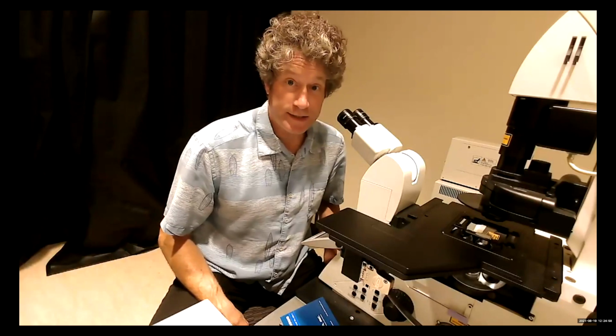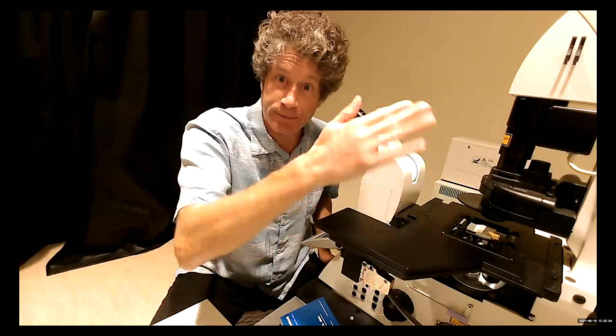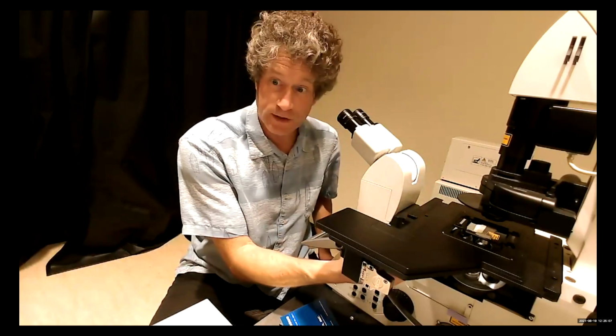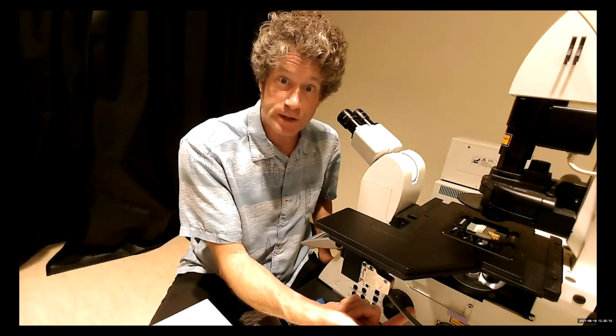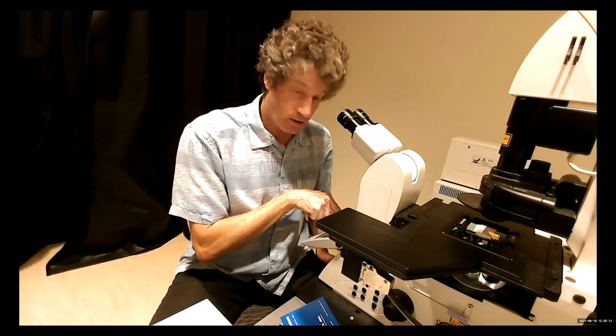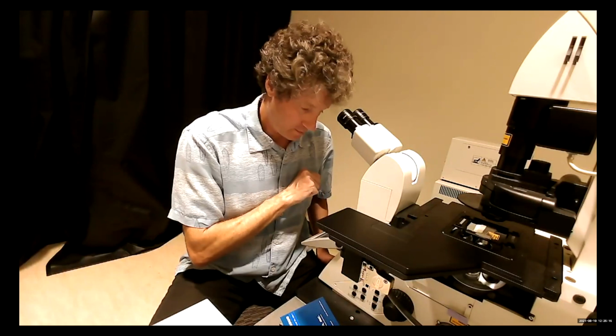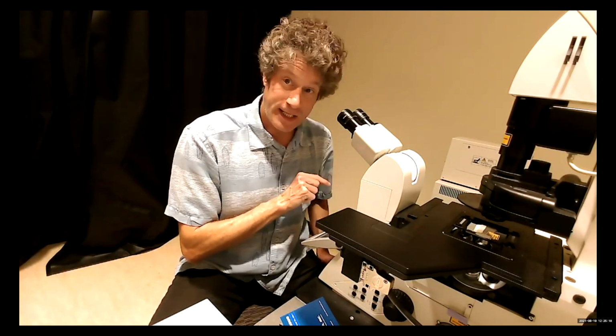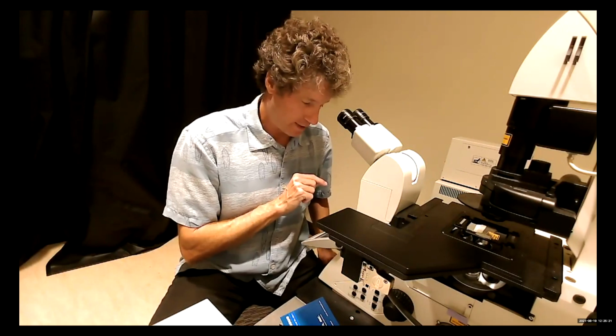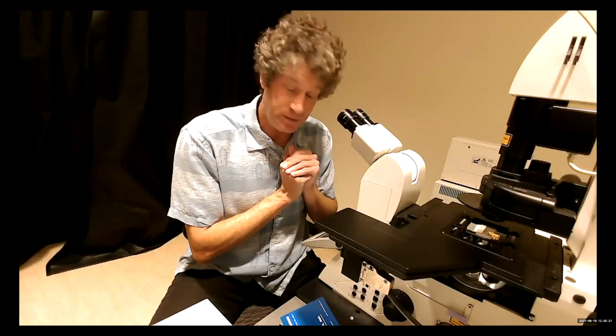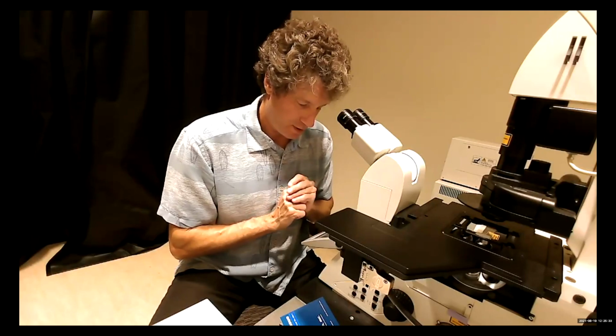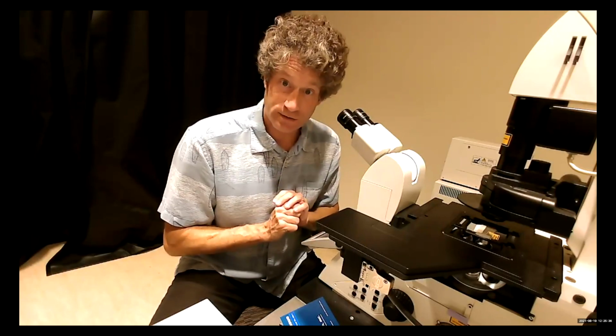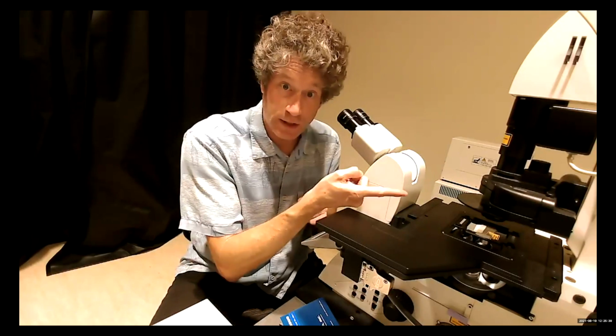Okay, now I'm gonna find the sample, which you should have seen on another video, but I'm gonna do it again. Basically, the sample is here, right? It's upside down. You wanna make sure the objective lenses, which are underneath here, should be 10X. That's here on the little lens icon. It says 10. Then you go up to the next icon, there should be BF that has a contrast, like a moon with a contrast light and dark on it. That should be BF, and TL shutter should be yellow. Then the very top, the TL axis should be clicked, and that allows all the light to come through, okay?